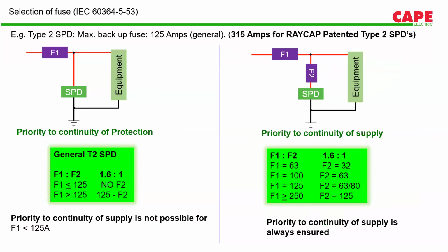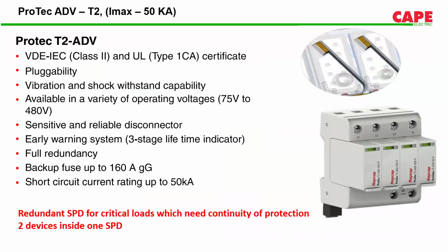In that case, there are SPDs which come with a backup protection device. You can see on our screen, these SPDs have a redundant SPD. That means once the primary MOV fails, so the primary protective device fails, immediately the secondary protective device will be under operation. So your equipment will always be protected and supply will be continued to your equipment.